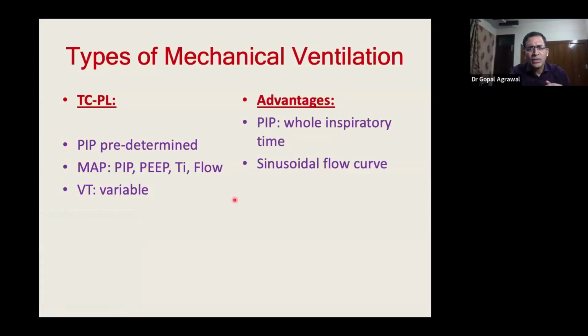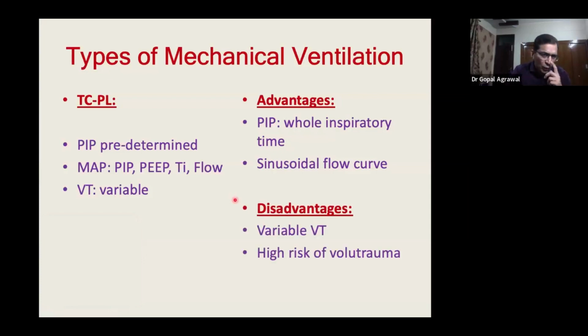Yeah. So the advantage of this is that the whole inspiration PIP is delivered throughout the inspiration time. That is a good point of TCPL. And the flow curve is sinusoidal, which we'll see in the next few slides. The disadvantage of this is that the tidal volume is variable. You cannot control the tidal volume.